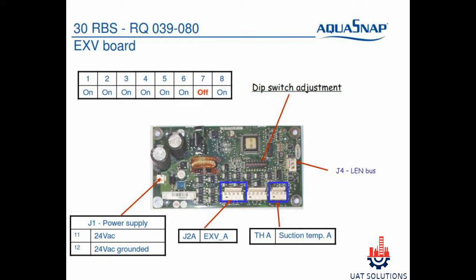EXV board DIP switch address for circuit A is shown. On section J1, 24-volt AC power is connected to power the board. On J2A, the expansion valve for circuit A is connected. On section TH, the suction temperature sensor for circuit A is connected.